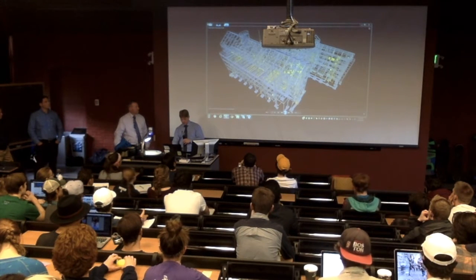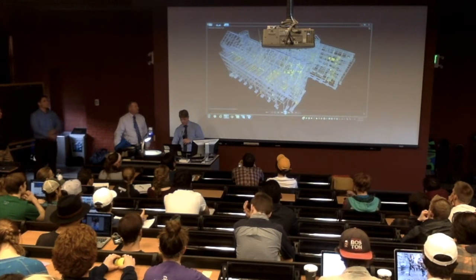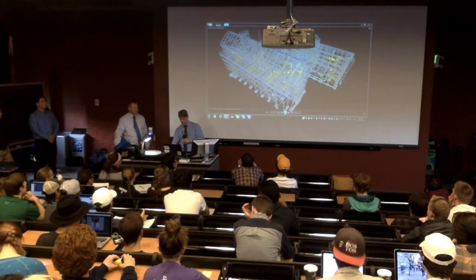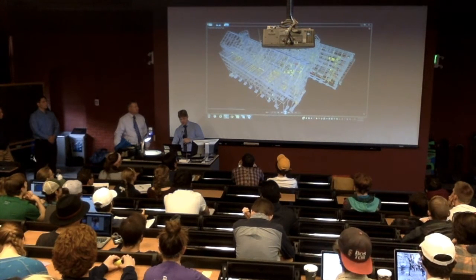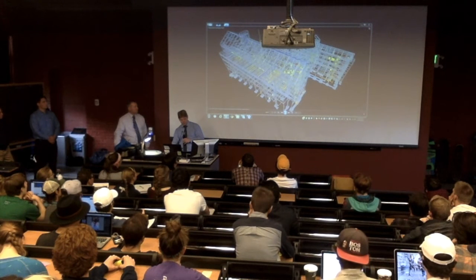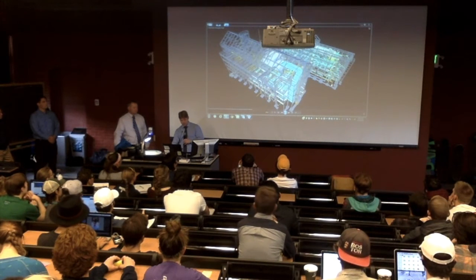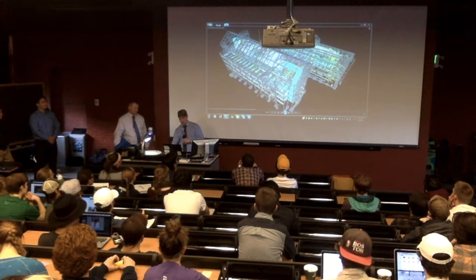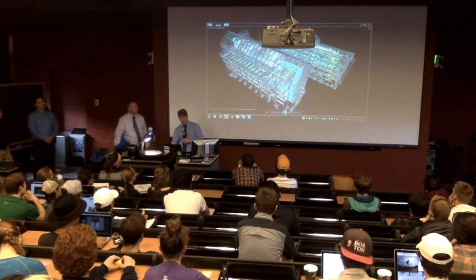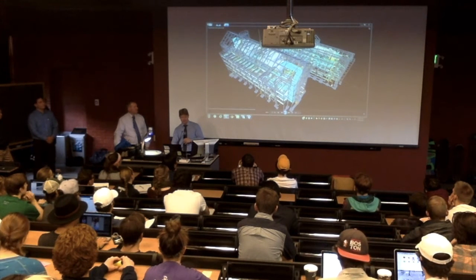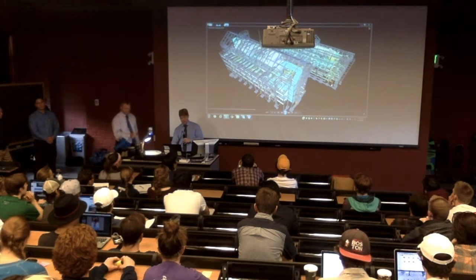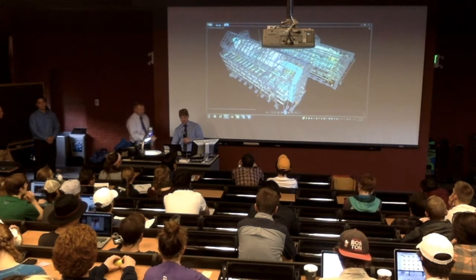So there's all the plumbing system overlay, and then it gets a little more complicated. You see the red is the fire protection. Again, just kind of one pump, one pipe system with sprinklers. And then you put the HVAC system on top of all that, and now you're looking at a giant mess of equipment and piping and wiring that all needs to be coordinated.